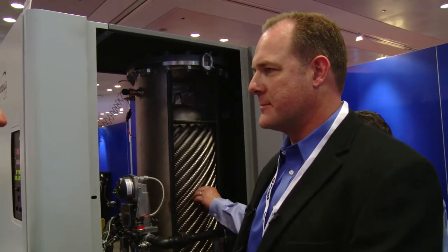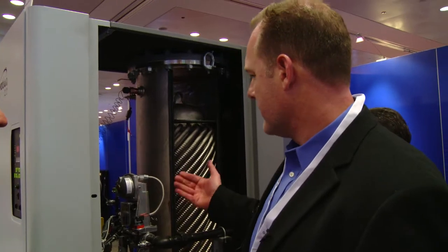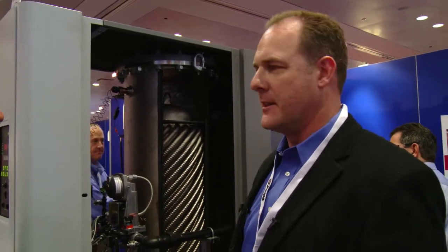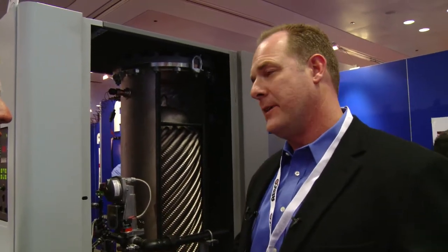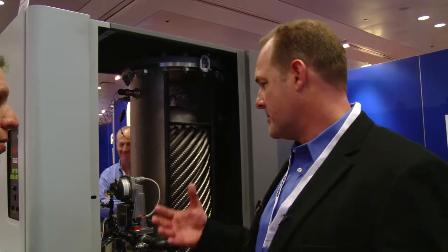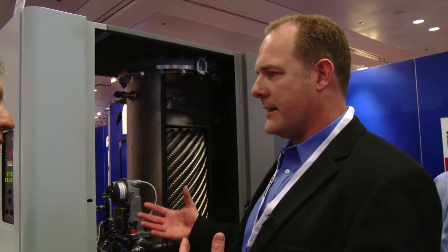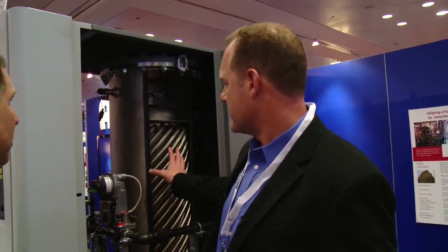One of the first measurements we try to achieve is uptime reliability. In fact, that's one of AERCO's core competencies, how we address uptime reliability. And again, when utilizing multiple heaters in a system and eliminating a storage tank, you're really eliminating that weak point in a system. So we actually design into our systems internal redundancy by adding multiple heaters.